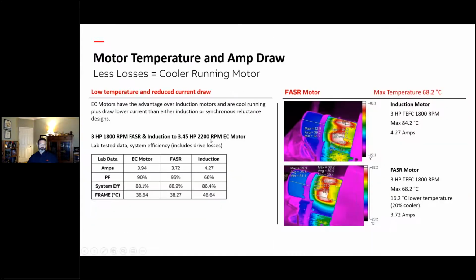This was only a 3-horse motor, so they just don't draw a lot of amps, but you can see an induction drew 4.27 amps. This design, because of the magnets, is doing 3.72. So high power factor, lower amp draw. In certain cases, the advantage of this is sometimes it'll allow you to do a smaller drive on it.